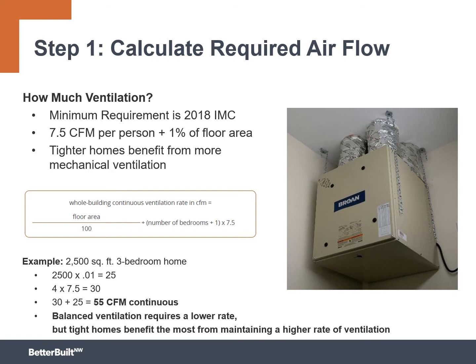So let's do a quick example here. Let's take a 2,500 square foot home with 3 bedrooms. So 2,500 times 1%, that's 25 CFM. 3 bedrooms means 4 people in the way that math is done in the International Mechanical Code. So 4 humans times 7.5 is 30. And that means we need a total of 55 cubic feet per minute if we were to ventilate continuously.